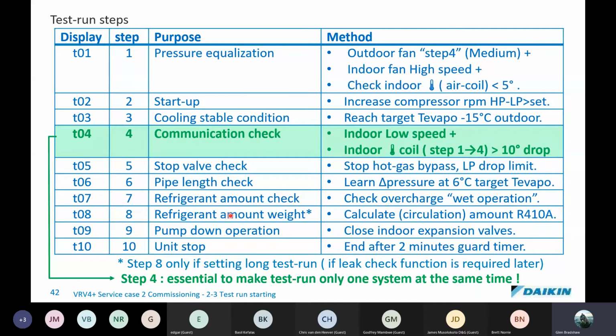Refrigerant amount weight, okay, this is T08. Calculate the circulation of the 410 refrigerant. T09 is a pump down operation, basically close expansion valves on the indoor unit, and T10 is the end, and this normally will display for about plus minus 2 minutes due to a guard timer, and then it will go off. Once these have all been satisfied during a test run, the system has completed the test, okay, and we can now do an operational test.